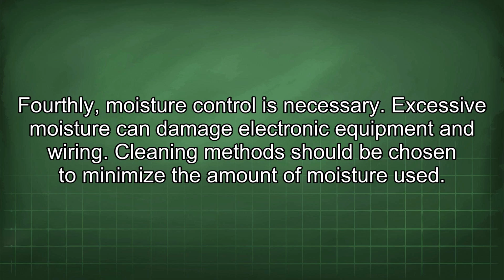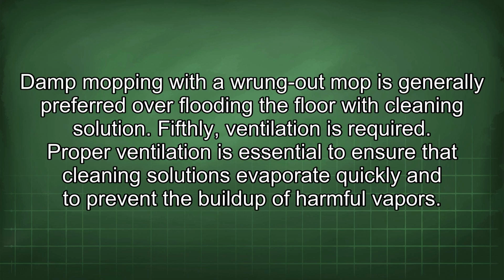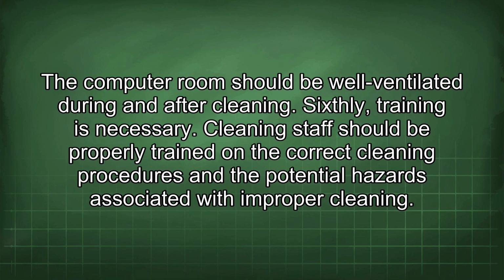Fourthly, moisture control is necessary. Excessive moisture can damage electronic equipment and wiring. Cleaning methods should be chosen to minimize the amount of moisture used. Damp mopping with a wrung-out mop is generally preferred over flooding the floor with cleaning solution. Fifthly, ventilation is required. Proper ventilation is essential to ensure that cleaning solutions evaporate quickly and to prevent the buildup of harmful vapors. The computer room should be well ventilated during and after cleaning.